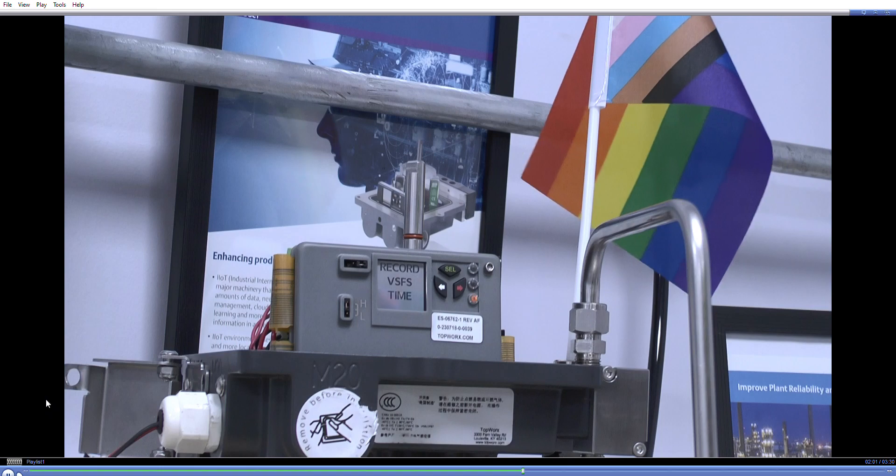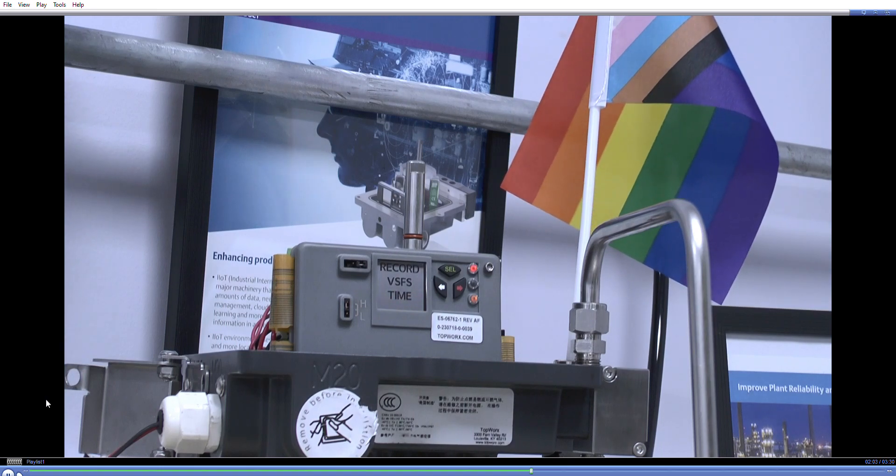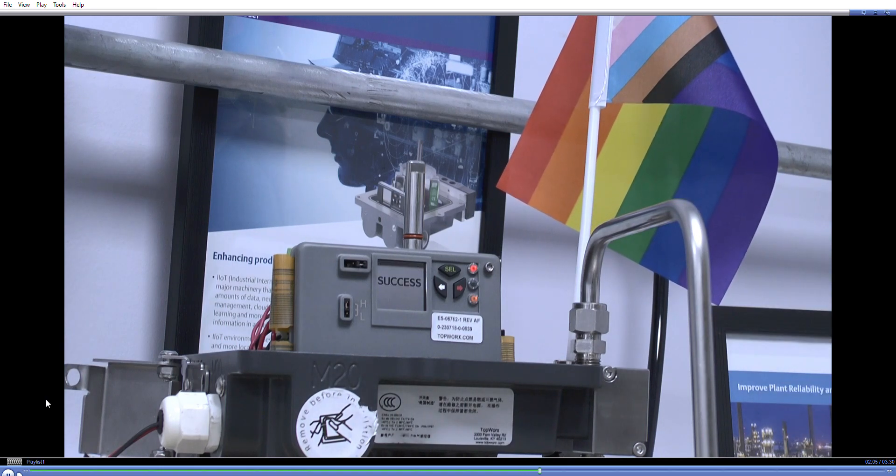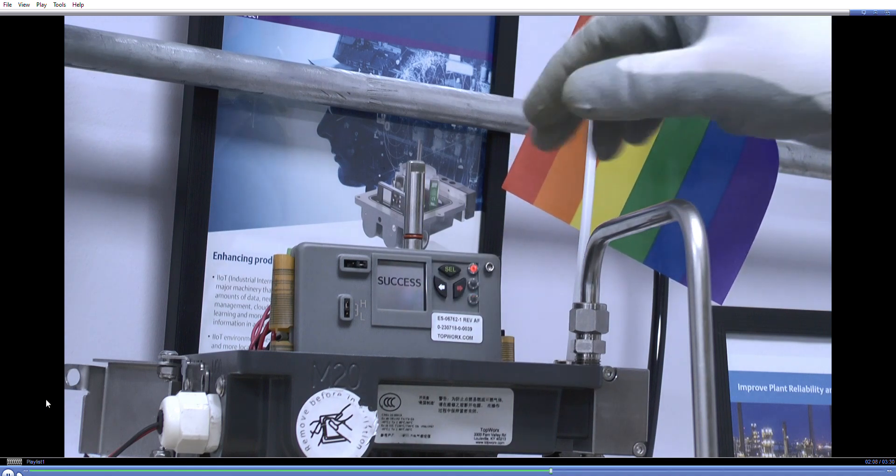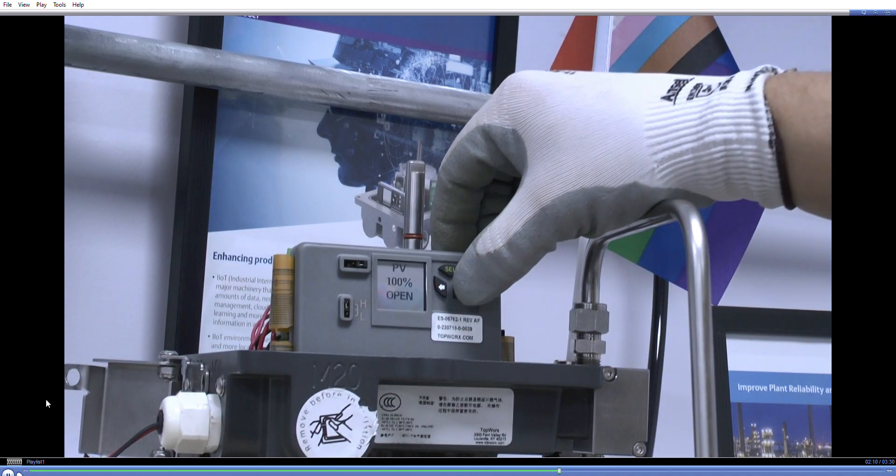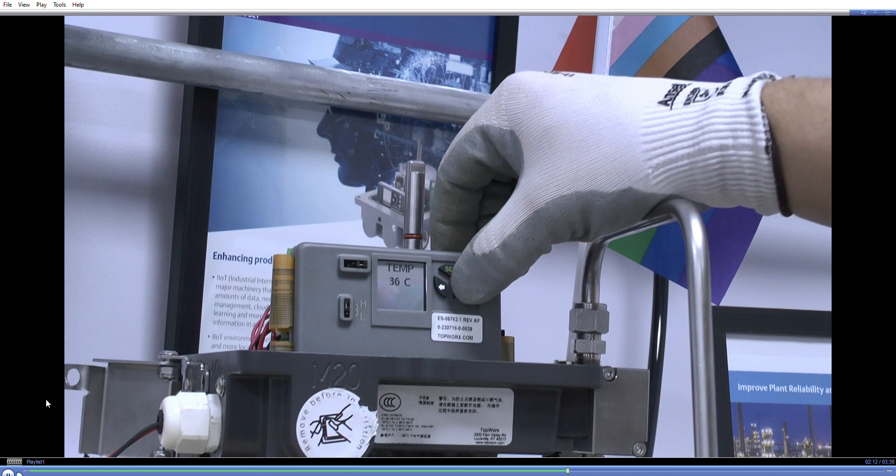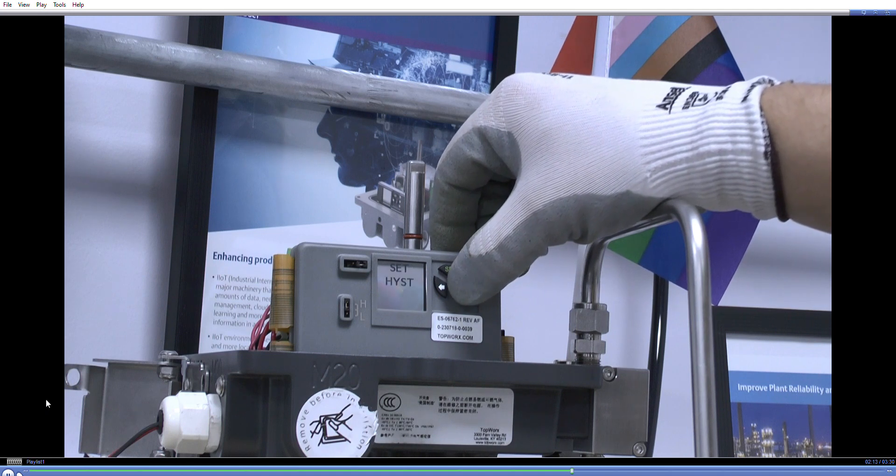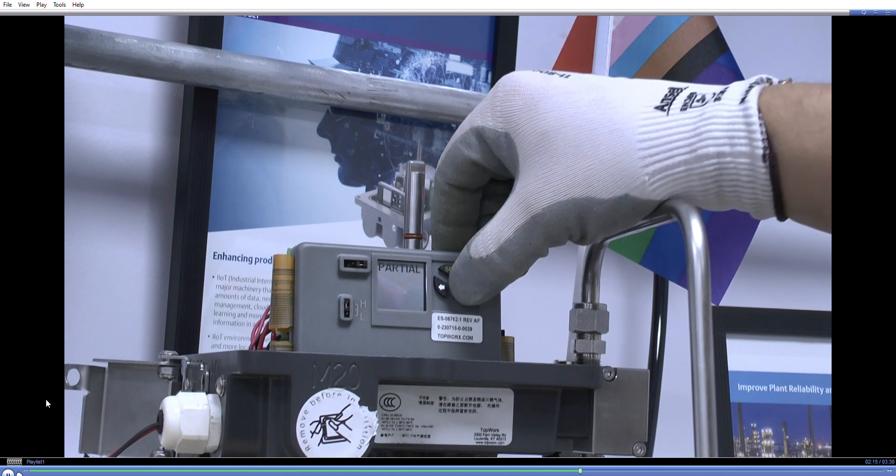And then part of the diagnostic features, what we're doing then is we're recording the time of the valve, how it operates. So that's completed the calibration test. The next test that we need to do is we need to calibrate the partial stroke, so we need to do a partial stroke test.